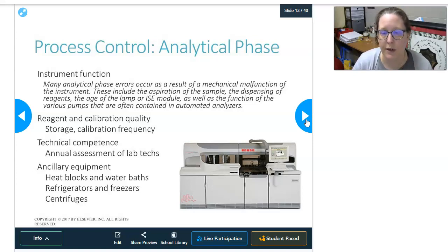This is usually what is provided to you by the manufacturer. You really don't want to go outside of what is provided by the manufacturer, even if it's supposed to be compatible. Again, reagents have to be properly stored, and you want to make sure that they are calibrated at the recommended frequency according to what the manufacturer recommends. Obviously, you would calibrate every new lot number, but sometimes if you have a lot number that lasts a long time, you may also have to calibrate them maybe once a month or something like that.